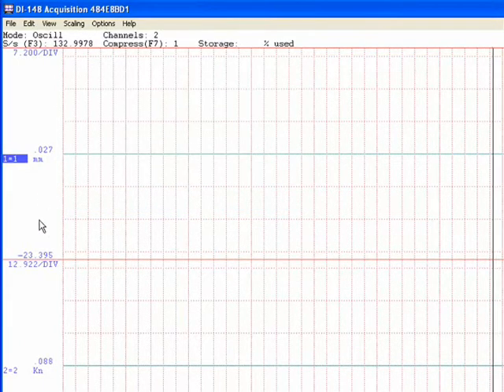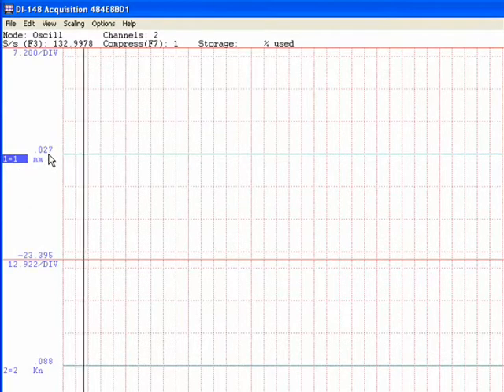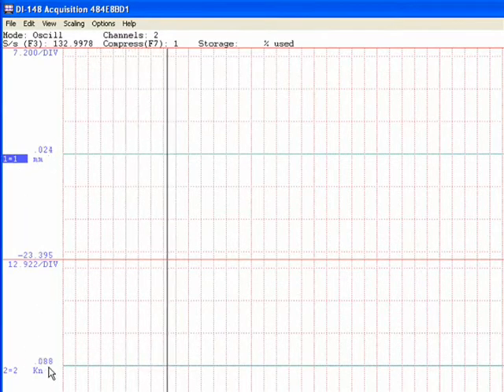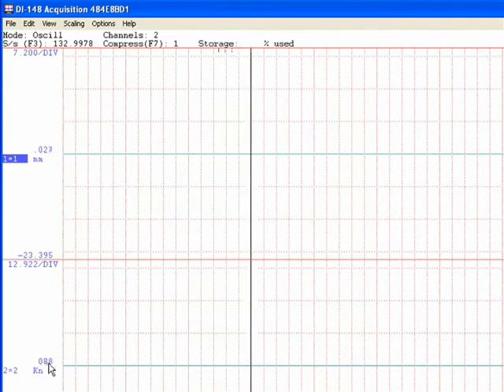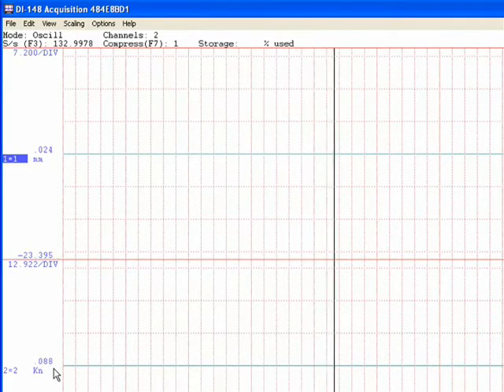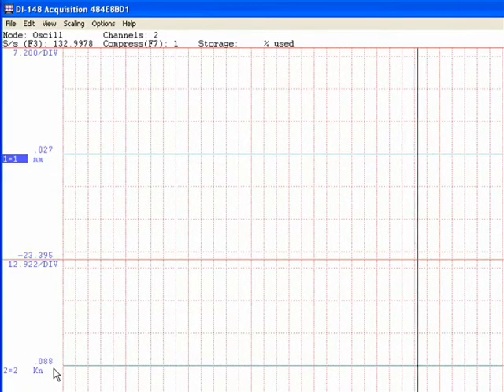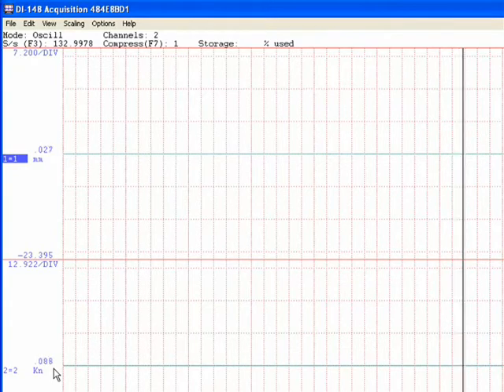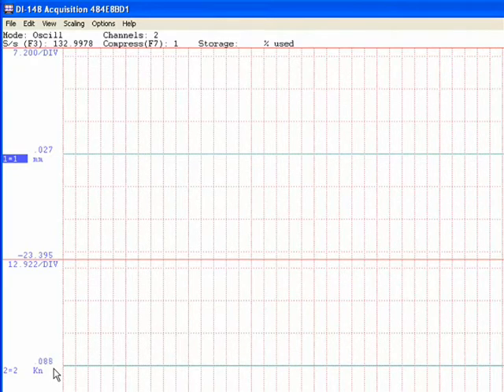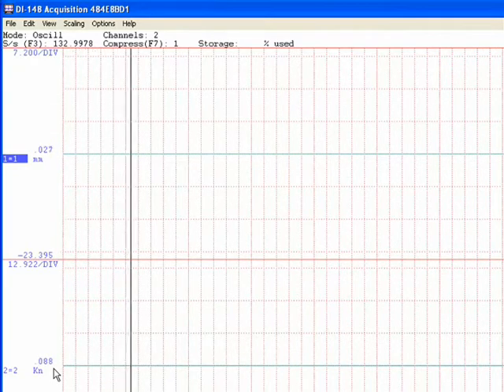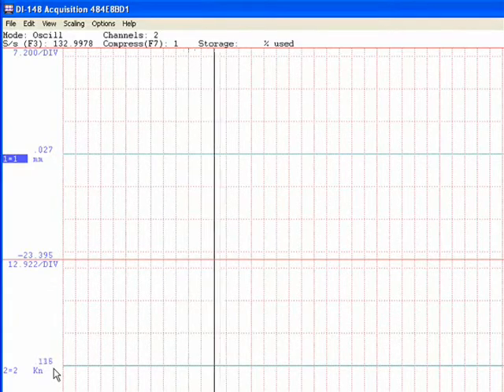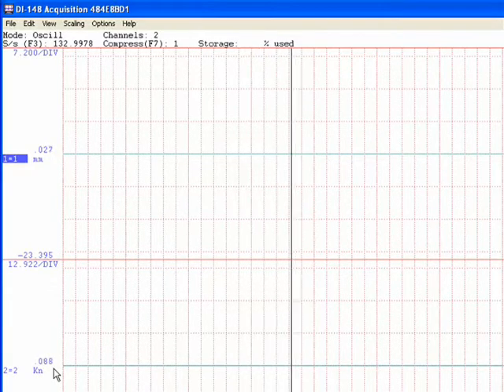Now, as you can see, this is the current reading of the transducer. What we have to do is zero out the calibration. You must understand this does not affect the meter or your transducers. All we're doing is synchronizing the computer program with your meters. We want them to be reading the same thing.